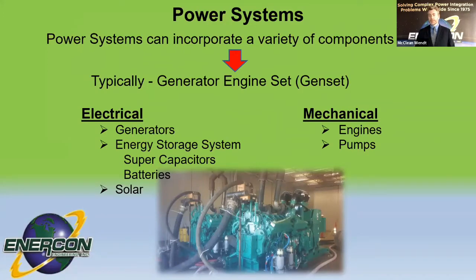So the power systems, typically what we're looking at is a generator engine set, and primarily, we test units that are between 0.5 megawatt to 3 megawatts, or systems that are in that range. And typically those are fueled by either diesel or natural gas. Although that's what we typically do, now with increased demand for microgrids and renewable sources, we're seeing an increase in addition of energy storage systems. It could be supercapacitors or batteries, and solar power integrated into these systems. In addition to those power systems, we've also seen specialty applications where engines have driven pumps, and all those we can test and verify proper operation before passing them on to the customer.